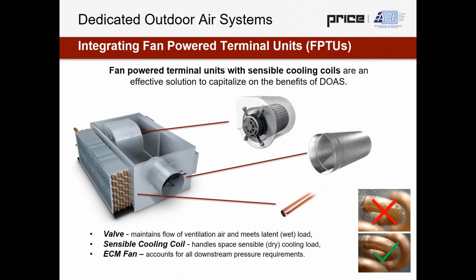Looking specifically at the product we're discussing today, the fan-powered chilled water terminal unit being integrated in this kind of system, why is it such a perfect fit for this dedicated outdoor air system layout? Well, all of the components are handled very effectively through this downstream air distribution solution. We have the primary air valve, which can maintain flow of ventilation air to meet the latent load and to provide enough fresh air for breathing.